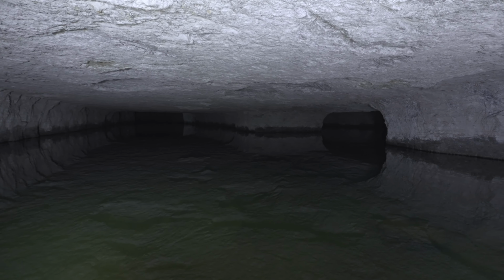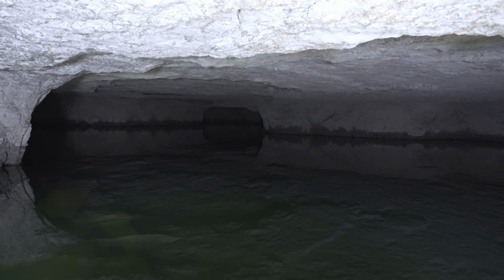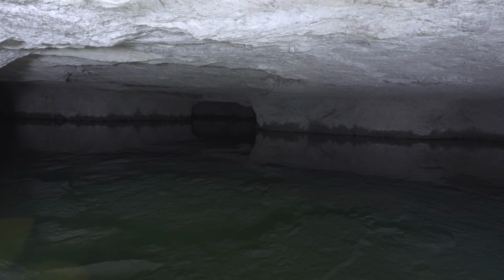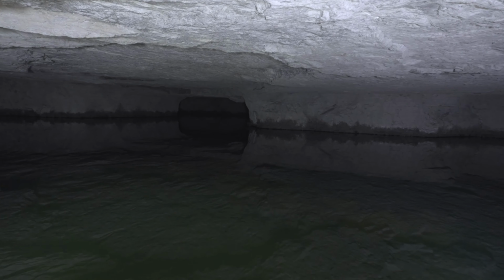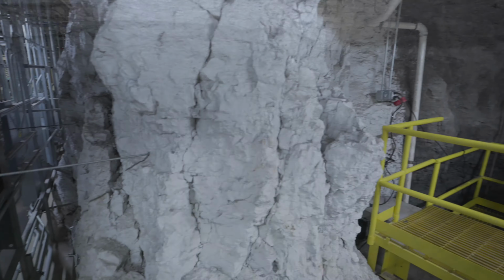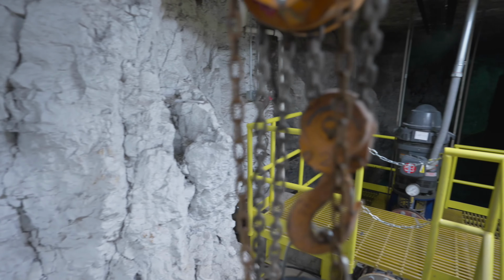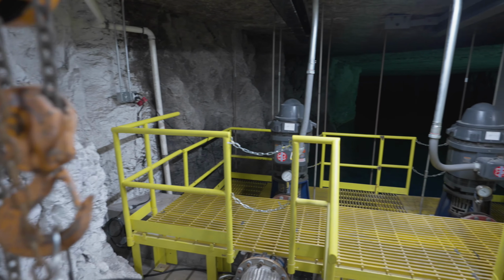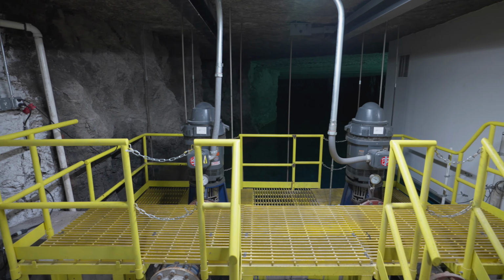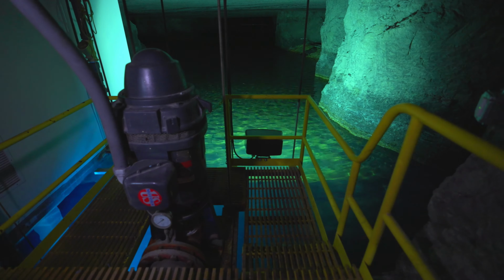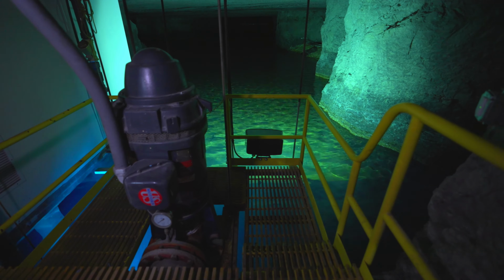Today, the underground lake is used to cool our facility and is the source for sprinkler systems throughout the facility. The geocooling system consists of three redundant pumps which pull the 53-degree water into stainless steel heat exchangers that support a data center chilled water cooling loop.